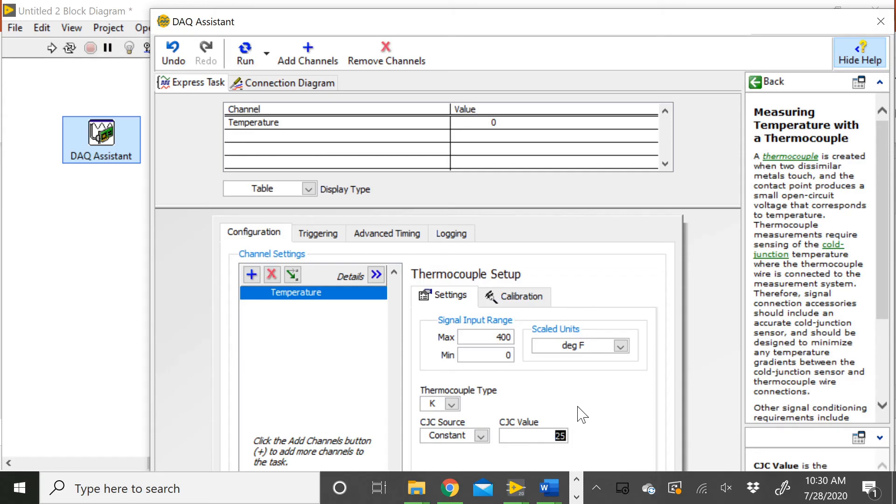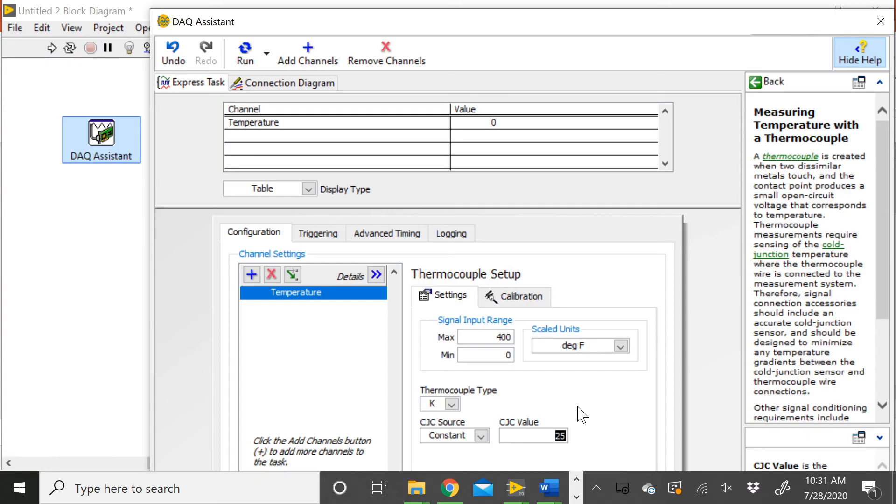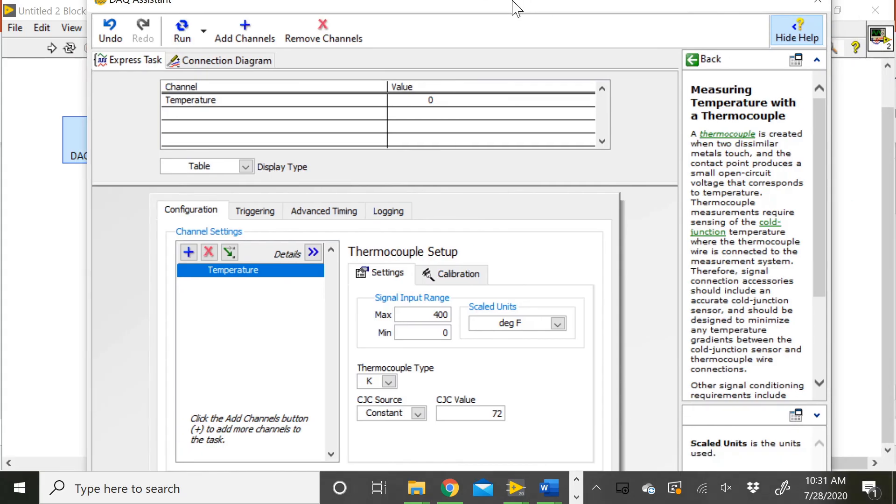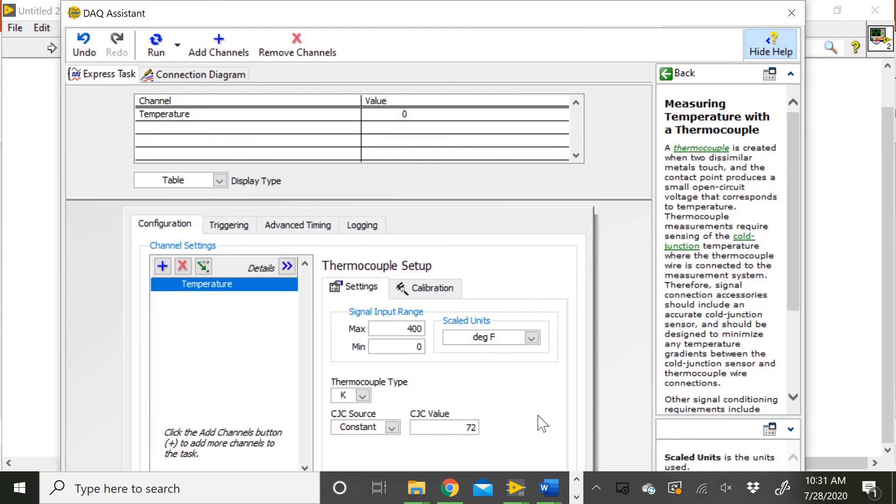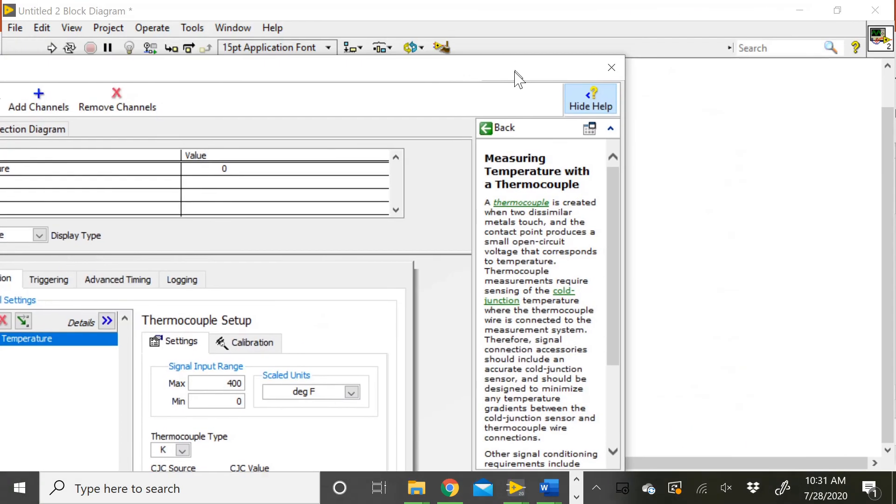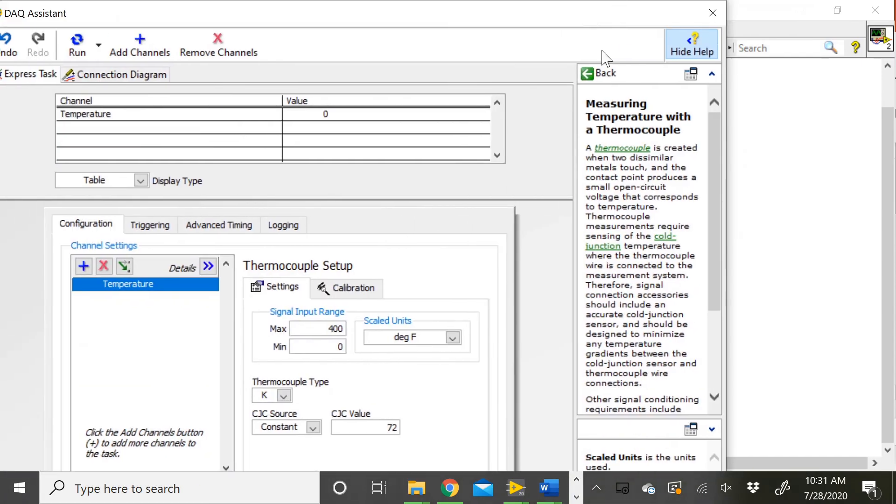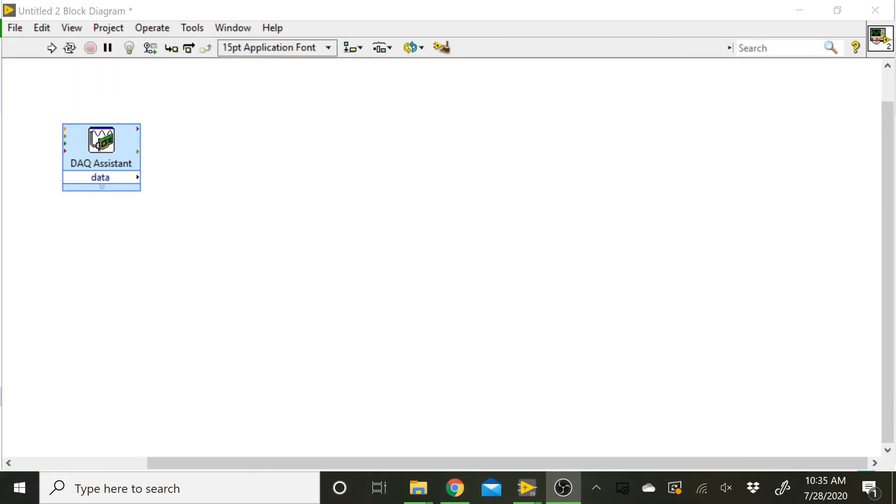This CJC value should be in the same units that the output is. So in our case, that would be Fahrenheit. We just want to tell LabVIEW what room temperature is. The cold junction should just be whatever the lab temperature is because that's where the cold junction is taking place. I checked the thermostat this morning. You can find the readout for that on the wall of the lab near the doors to the lab. There's a series of thermostat settings, and you can go and find that value. This morning it was 72. We can adjust this value later on if we find that we're not getting the correct values there. We can accept the changes here. There's an OK button down here that's popped off the screen, so we'll have to figure out how to click that one.